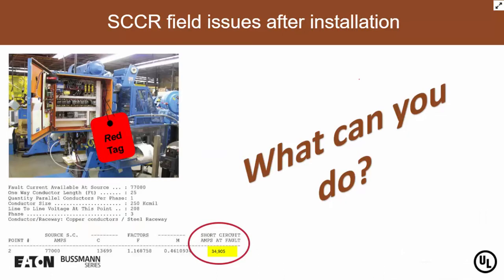All right, so I deal a lot with industrial facilities where they have machines that are over-duty, if you want to say. So in this case here, this machine is rated for 10 kA. And the available fault current is almost 35,000 amps, just under 35,000 amps. And so what can you do? That's where we have to consider what we can do to boost up this SCCR, because right now we're in violation of the code, we're in violation of UL 508A, and we're in violation of NFPA 79, but mainly because we're in violation of the code and because of arc flash. And we're going to talk about arc flash down the road a little bit.